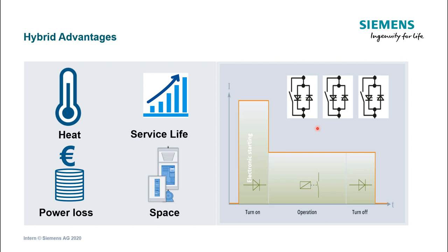So where does the benefit lie when you're comparing against, say, a variable speed drive? Well, if you're switching a motor at full speed, at 100% of its operational capacity, then the soft starter is the most efficient way of switching your motor, because there's no energy savings to be made.